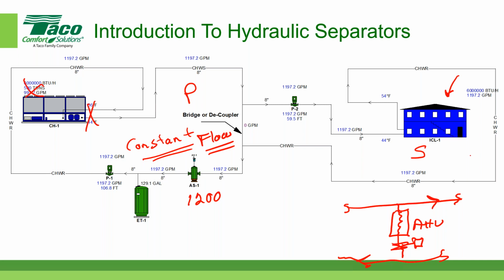So we have a bunch of two-way valves here, and as those two-way valves modulate towards the closed position as a function of reduction in load, then we probably have a variable speed drive on the pump, which means that we would have perhaps a flow of, I'm going to say about 20%. Well, 1,200, just check my arithmetic, Brett. If I had 1,200, I would go from a minimum flow of about 240 gallons per minute up to a maximum flow of about 1,200 gallons per minute. And that would be the range that I would have for the secondary circuit.